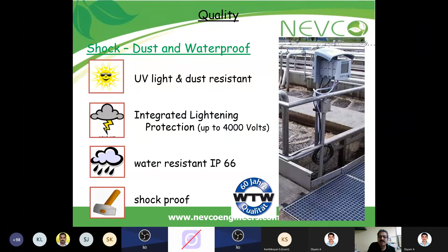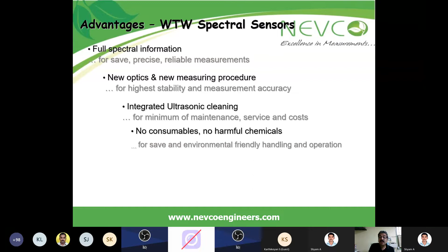So the advantages of WTW sensors are full spectrum information for precise, reliable measurement, new optics, and a new measurement procedure for the highest stability and measurement accuracy. Integrated ultrasonic cleaning means minimum maintenance and service cost, no consumables, and no harmful chemicals required, so it is environmentally friendly and easy to operate. High-tech materials like titanium and PEEK suit every application, from any sewage treatment plant, a small one or a big one, or anywhere. Now this is certified by TUV Germany.